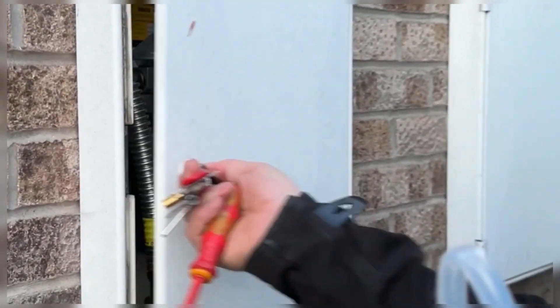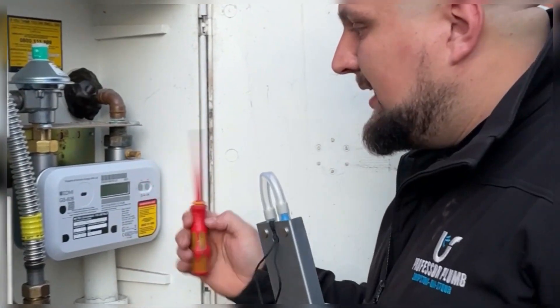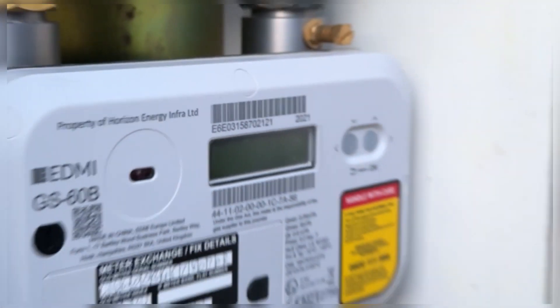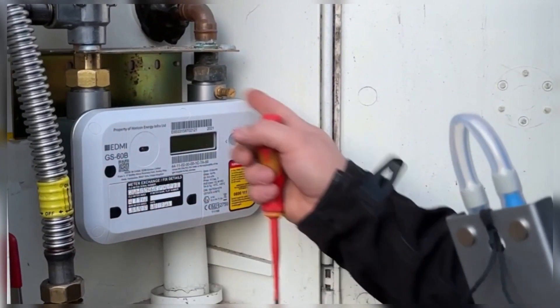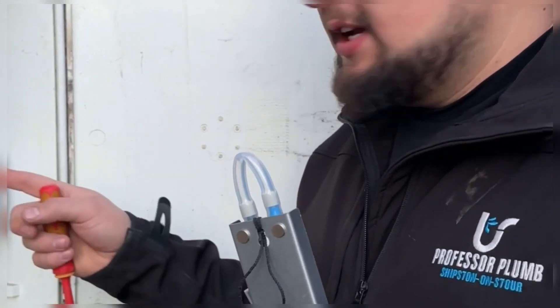Things to remember if you're going to do a tightness test is you need to check the appliances. So go turn any boilers off or lift up any cooker hoods, anything like that, because you need to make sure that you're testing the full system when you're doing your tightness test. So we've got our meter key. Let's have a look. First thing we need to do is identify what type of meter it is. On this one, if you actually have a look, it's the first two letters of numbers, so we know that this is an E6 meter.